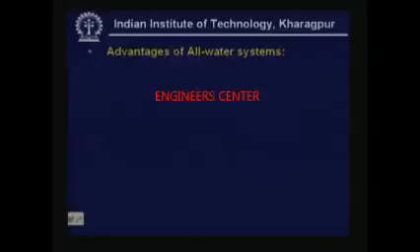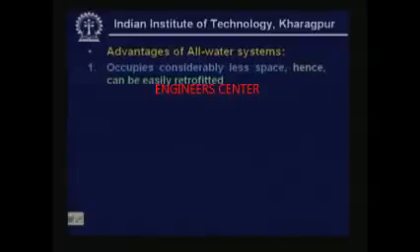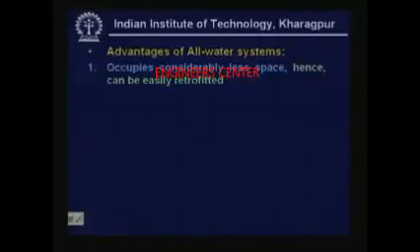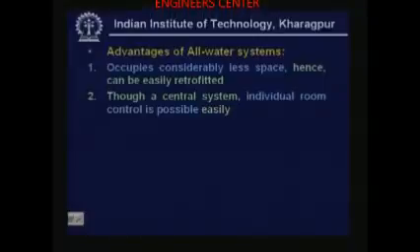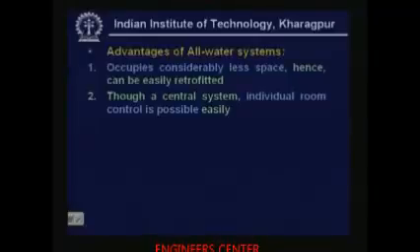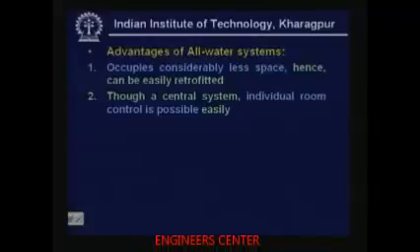Now let us look at advantages of all water systems. All water systems occupy considerably less space because there are no air ducts — only water pipelines, which are very small due to water's high density, resulting in much smaller volumetric flow rates for a given capacity. Hence the required space is very much less, making them easy to use in retrofitting existing buildings. These are central systems, but they also offer individual room control — for example, in a room where cooling is not required, you can simply switch off the fan of the fan coil unit.